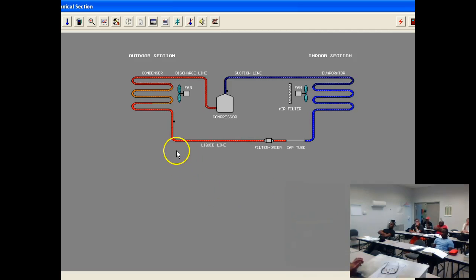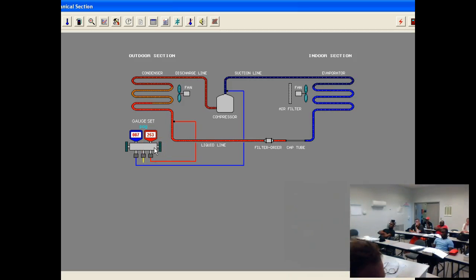First thing I like to do, if it's running, is put my gauges on there. So up here on the left corner, we have a bunch of tools. I'm pushing my gauges. My gauges say 253 and 87, I believe. Now, 256 and 85. Just like in the real world, you can look at your gauges and read pressure. But most of your gauges have a refrigerant scale that gives you a PT chart, right? At what temperature does it turn to a liquid? At what temperature does it turn back to a gas, given that pressure? If you click on it, it'll show you that temperature. So right now at 267, this refrigerant turns to a liquid at 122, just like you would read on your gauge. Anywhere on the gauges there. The 79 pounds on the suction side is turning at 46 degrees.